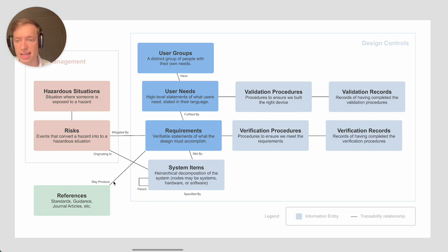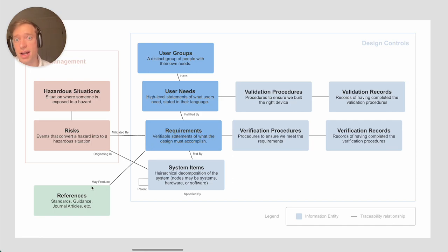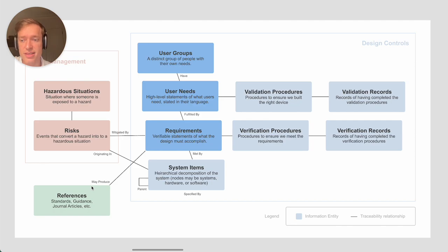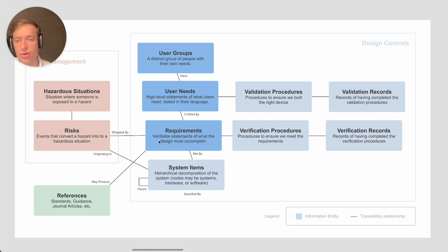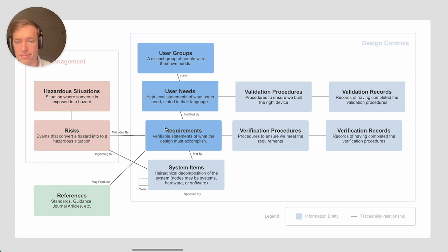This isn't really dictated by standard that you have to do this connection, this traceability relationship. But we find often there are FDA guidance documents for particular types of devices or standards that will dictate a number of requirements, and it can be very useful to trace those back to the standards where those requirements come from.